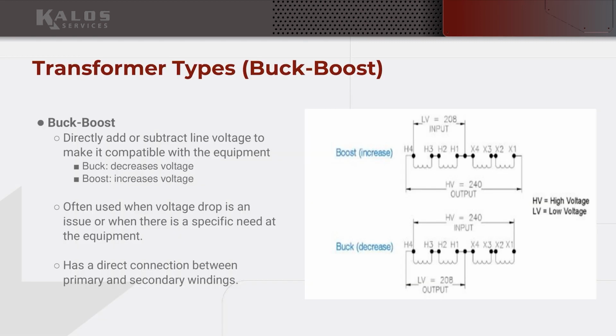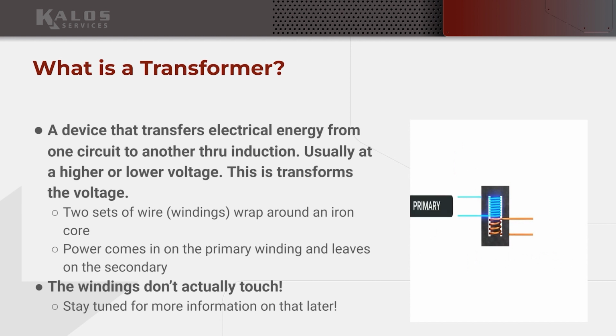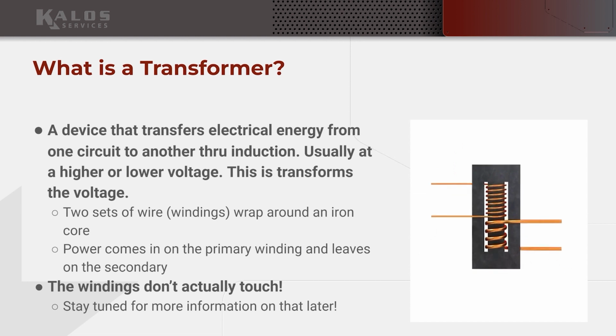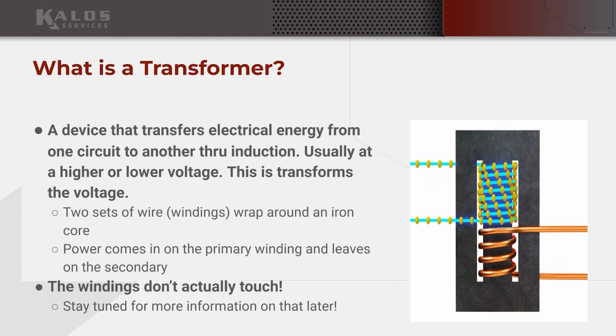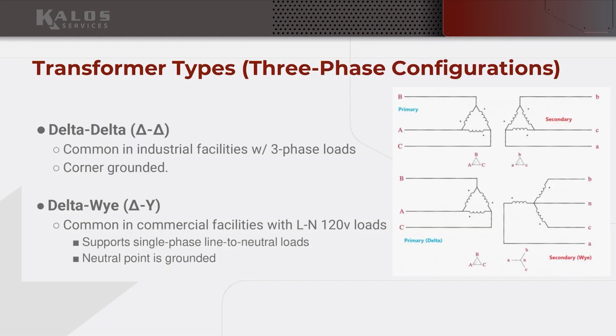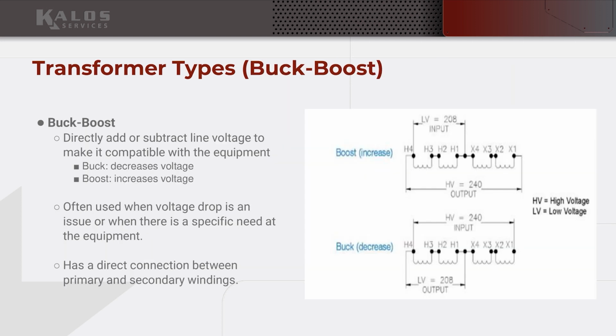And then there's another type of transformer that we would install occasionally called a buck boost transformer. And so the big difference with a buck boost transformer is, if we go back and look at this illustration, we see there's no connection between the primary coil and the secondary coil. It's only connected through the inductive coupling there, right? There's no wire connection in this one either. We can see primary coming in on one coil, secondary goes out on the other coil. There's no direct wiring connection between these. Whereas with a buck boost transformer, there is.